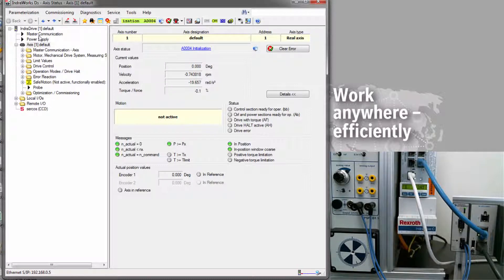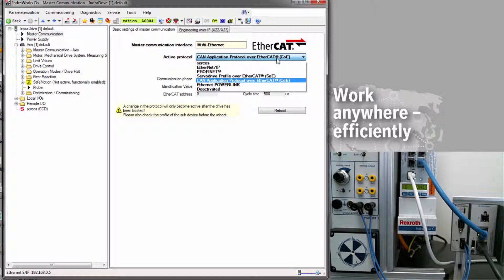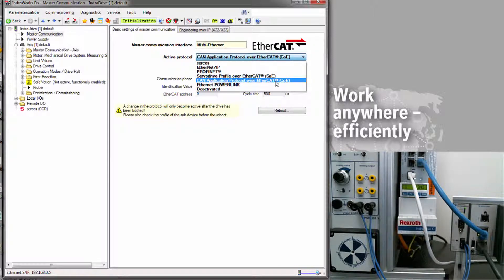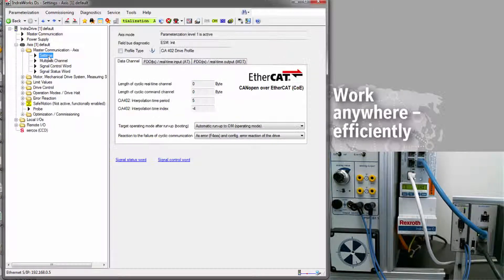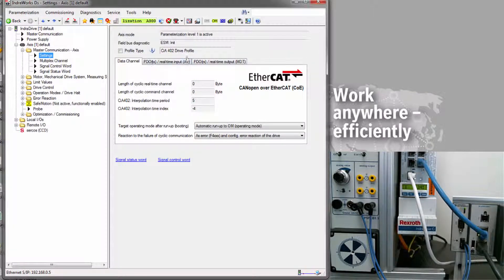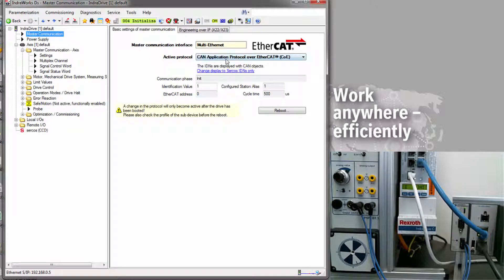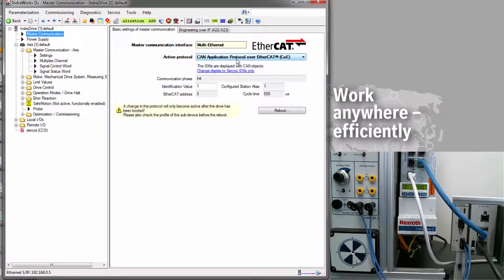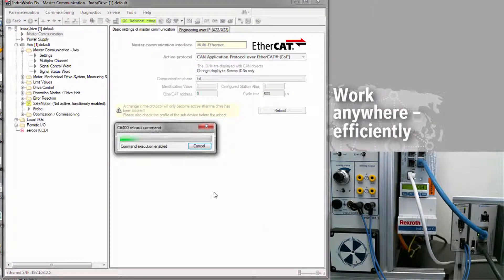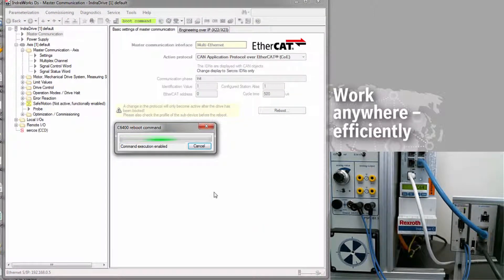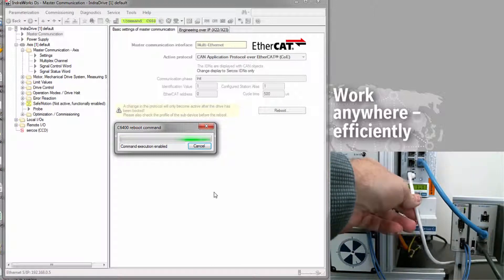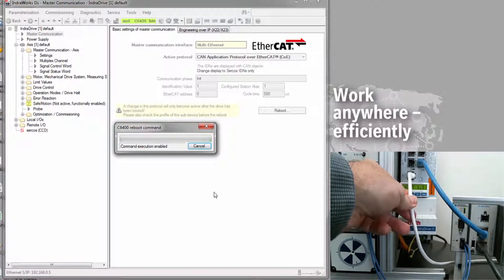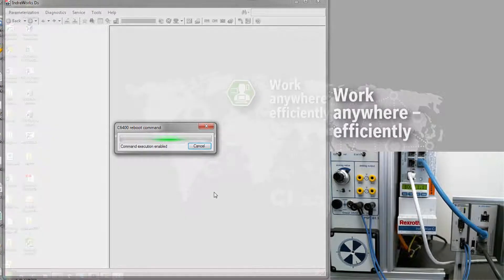If I come up here to Master Communication, I need to make sure that the active protocol is set to EtherCAT COE. So this is CAN application protocol over EtherCAT, and I need to verify that in the settings, I have the CIA 402 drive profile selected as active. This is configured automatically by the software once we've selected EtherCAT COE. Once you've made those selections, click Reboot, and the drive will reboot with EtherCAT as the active protocol. Once that's done, you can remove the connection to the engineering port. We won't need that anymore to do Soft Motion programming.